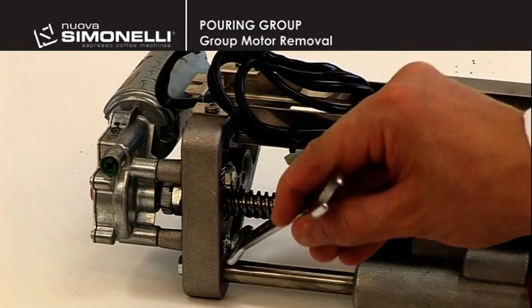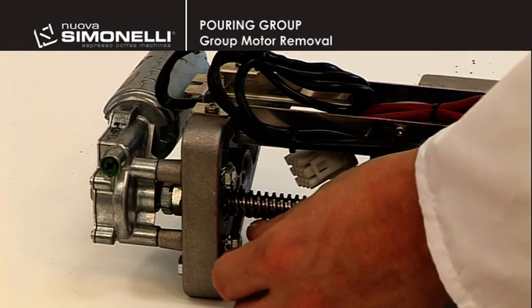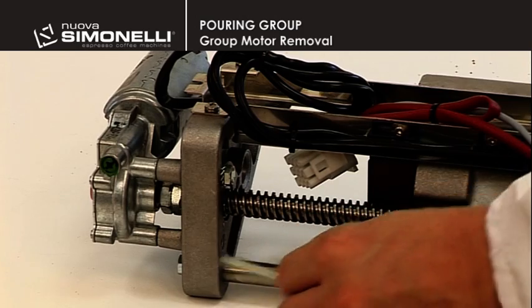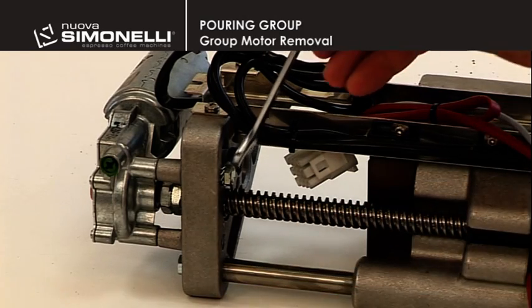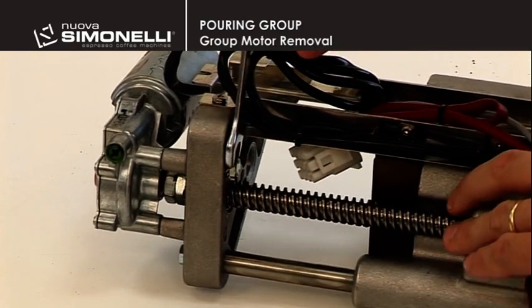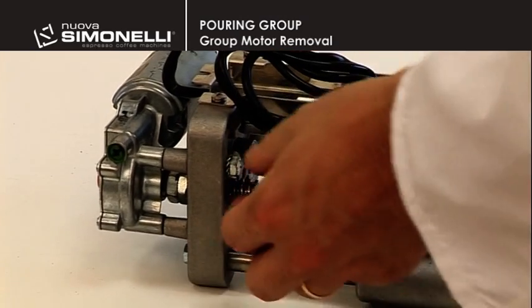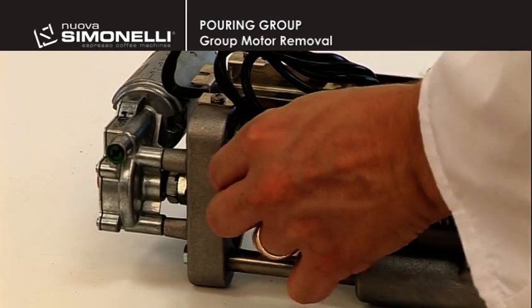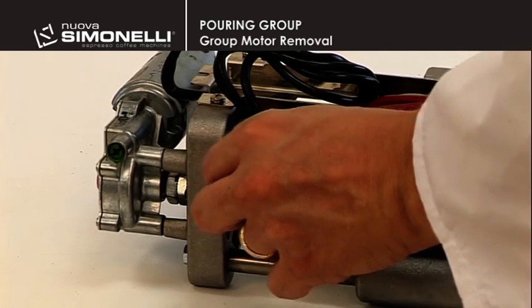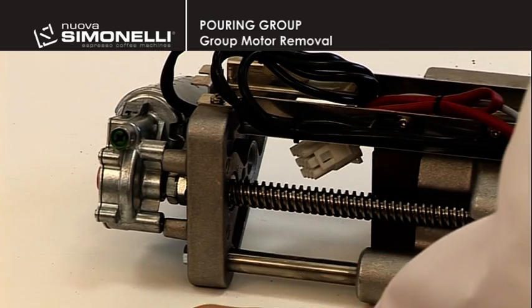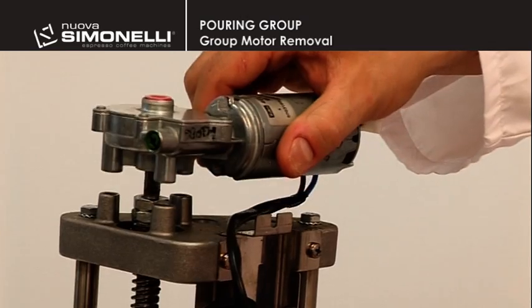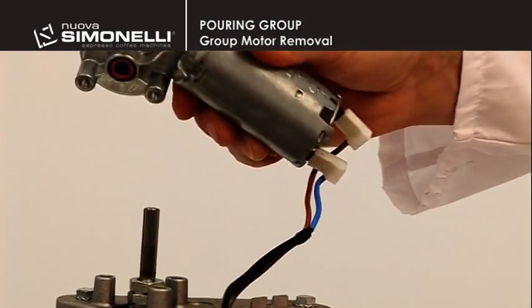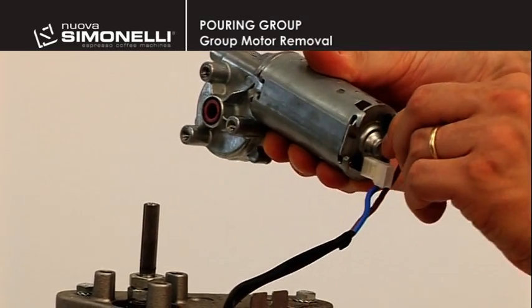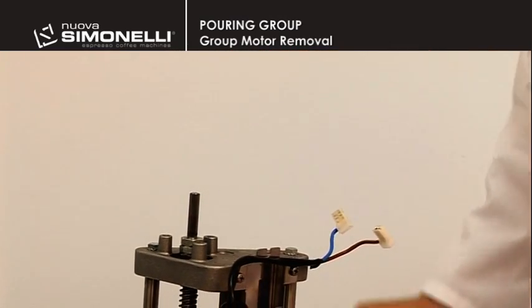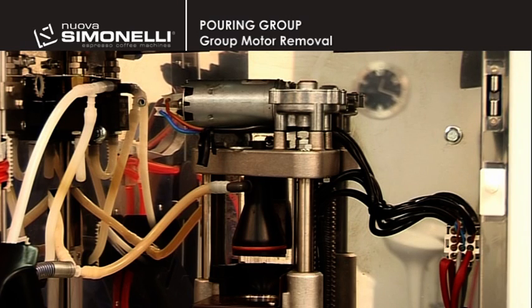Group motor removal. The service engineer now needs to remove the two screws at the top, under the upper motor bracket, with a 10mm wrench. Slide out the motor and the supply faston connections. This operation can be carried out with the group fitted to the machine and following the same procedure.